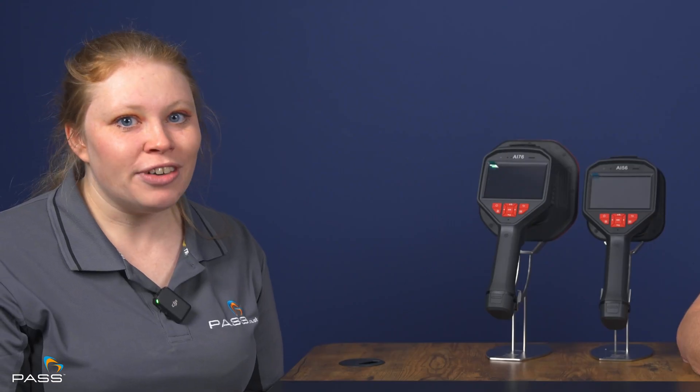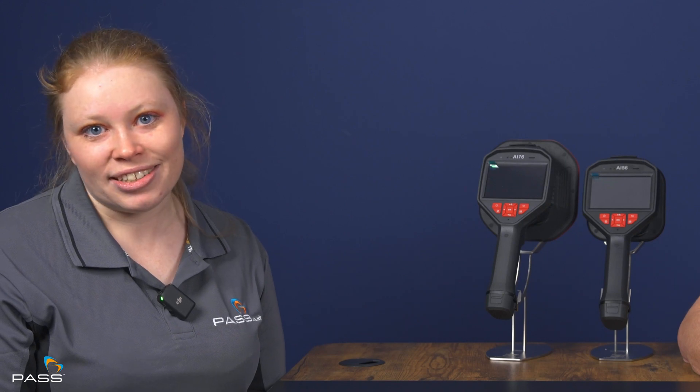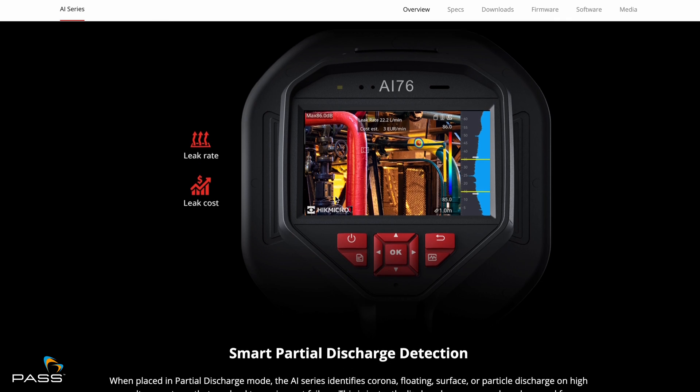You can click the box above to download HIKMICRO's acoustic camera brochure, which contains specifications for both models. The AI76 is roughly £2,000 more expensive than the AI56 — why is that? As you can see, the size of the microphones differs: one has 64 microphones, the other has 134 microphones. The extra £2,000 gets you the ability to hear lower rates of energy loss or gas leakage. So sensitivity is a real key factor with the AI76.